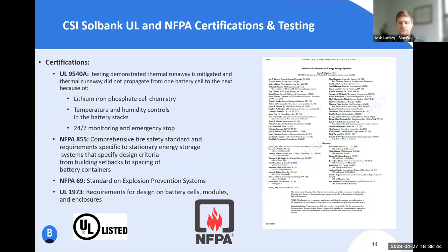Additionally, there are UL standards, most specifically UL 9540A, the testing standard for thermal runaway fire propagation. This testing standard was developed specifically to address the primary underlying concern regarding thermal runaway as a cause of fires. As part of UL testing, an individual cell is effectively forced to enter thermal runaway, and there's testing at the cell level, the module level, and the unit level—the unit level being a single enclosure. Then you look at the test results to see what happens in each case: does thermal runaway propagate, and how does that inform design features?